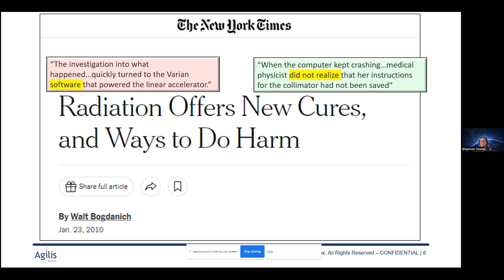There was an aperture that should be closed, so it was doing an imaging and then a delivery of radiation. And the arm that should have been attenuating that radiation wasn't in place. It was quickly identified that part of the error was software, but also the computer kept crashing. The user programming it didn't realize that the updates they had made weren't getting saved. They were getting vague error messages. The state of the system wasn't the same as the user thought it was.